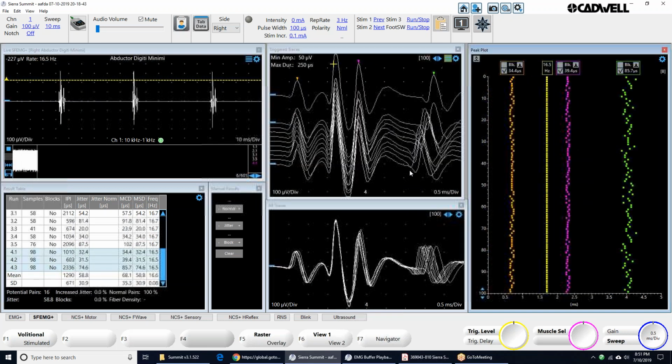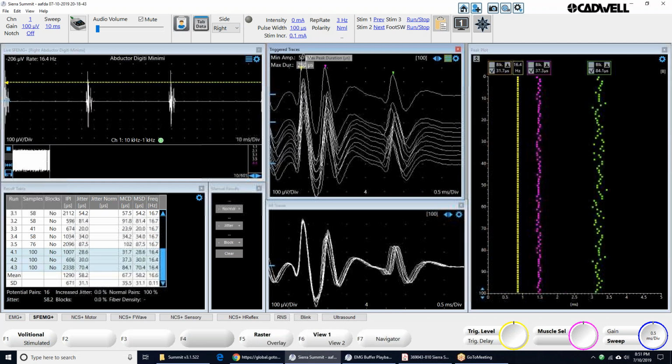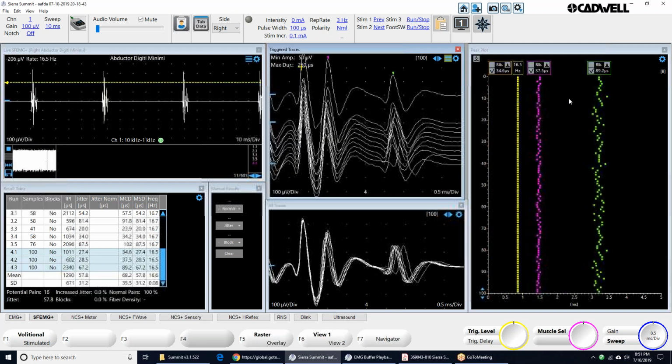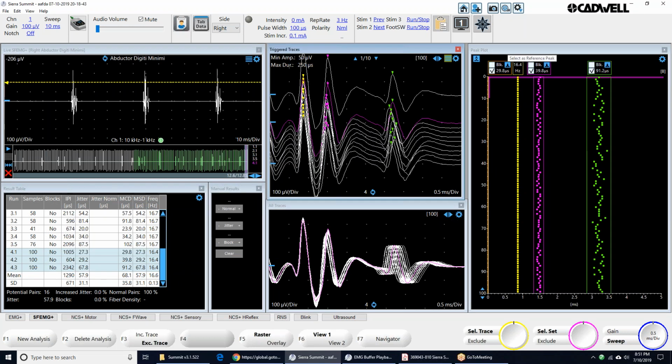In some cases, maybe in a situation where you're only seeing 3 of the peaks, okay? When you stop it, you're seeing 3 peaks here, but it's recording 4 peaks. So always make sure that you can see all the peaks in this window that it's recording, because otherwise you could have a peak that's off the screen somewhere that's not a real peak, and it's affecting and causing your other data to be excluded, in which case you would just uncheck that peak.